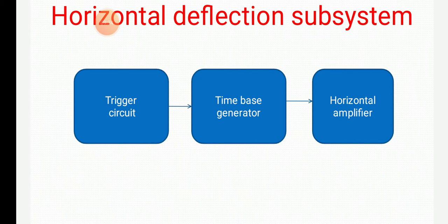Third one is the line signal. It is derived from the frequency of the power line, that is 50 Hz. Whenever the waveform has a fixed time relationship with the line frequency, this mode is preferred. Means what? Line. Directly it will provide the AC signal, that is 230 volt 50 Hz, and the time and the waveform should be fixed. So for that purpose you use the line. So this is a fixed relation. 50 hertz is the standard.